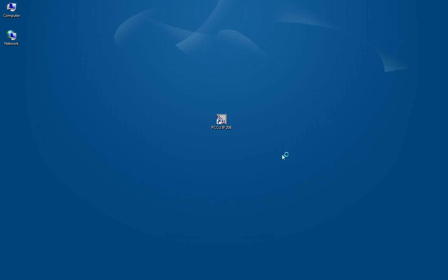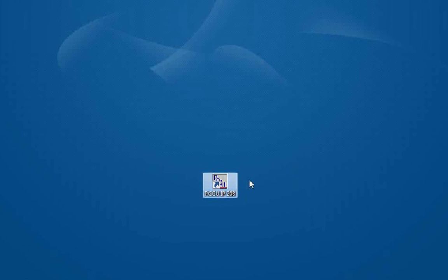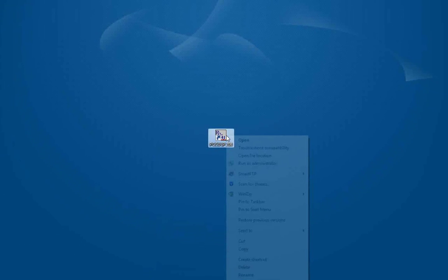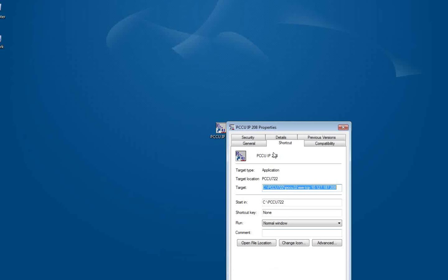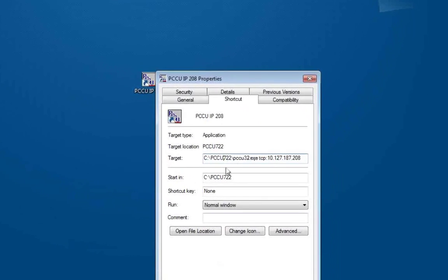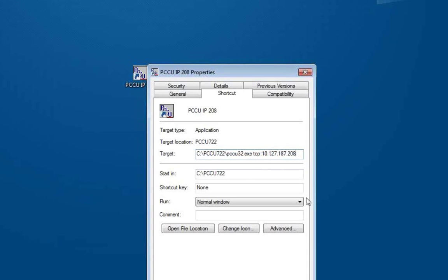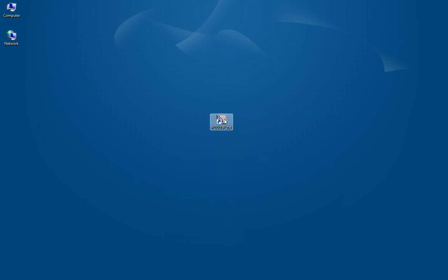We'll begin by connecting to a G4 meter. Here on my desktop I have a PCCU icon and I'm going to connect Ethernet to a G4 meter. If I do a right click on my icon and go to properties, I have my target line here that's pointing to wherever my PCCU32.exe file resides, followed by a space, TCP, colon, and then the IP address of my G4 meter. I hit apply and then say ok.